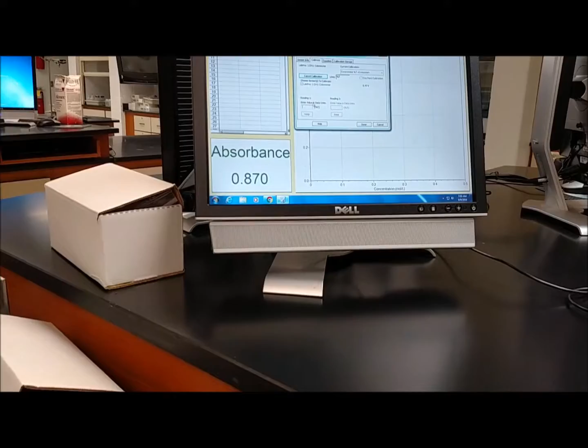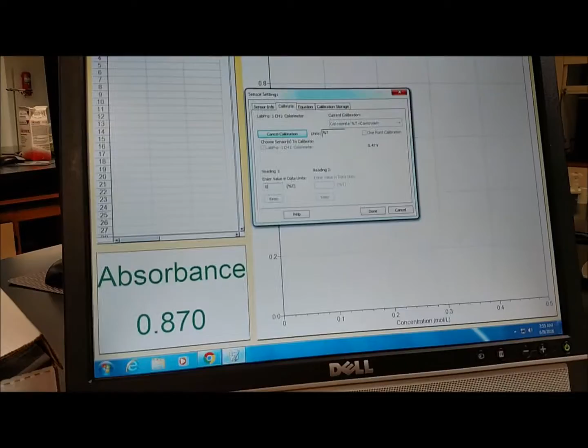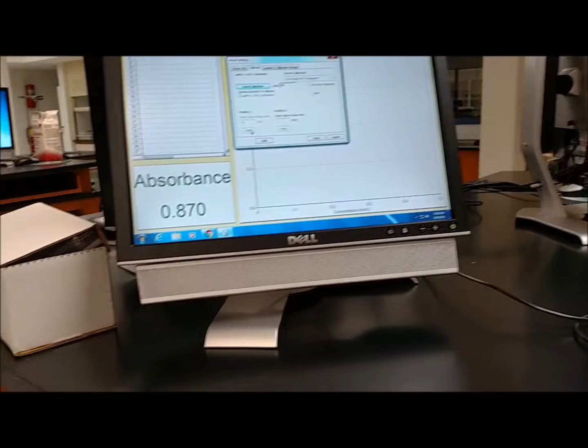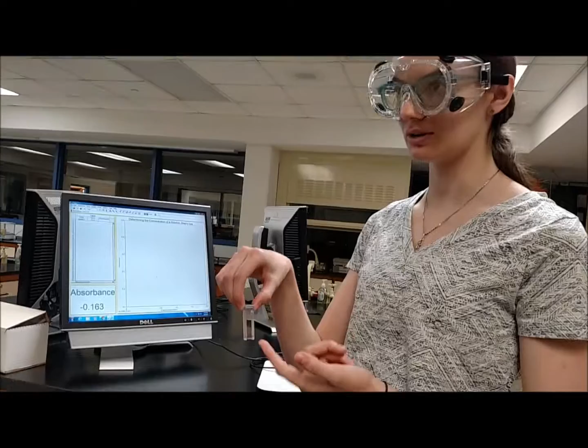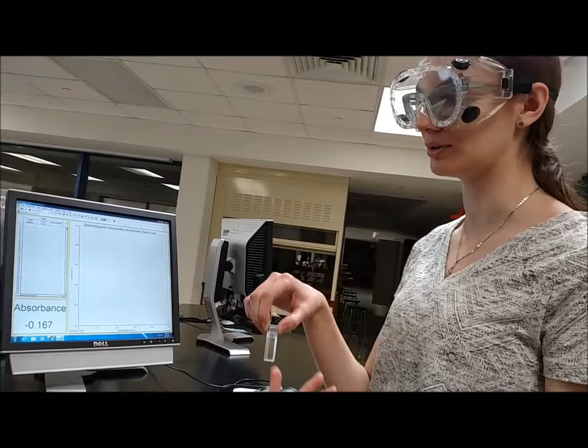wait till it's constant, and then type in 0 into the box, click keep. Next you switch it to green, wait until it steadies, which it has, and then you type in 100, and then click keep. Then you just simply take out the cuvette, get rid of the water, and then repeat the same process using whatever solution you have. So you take out the water, put in your solution, put it into the colorimeter, get the reading, and so on and so forth.